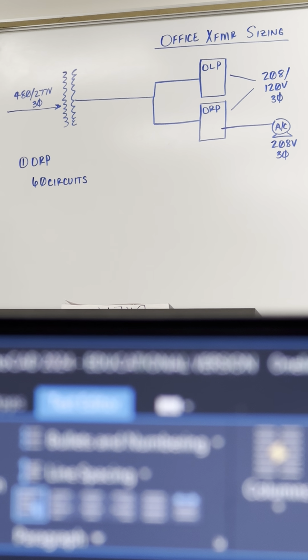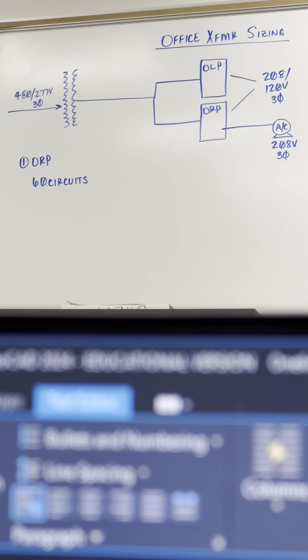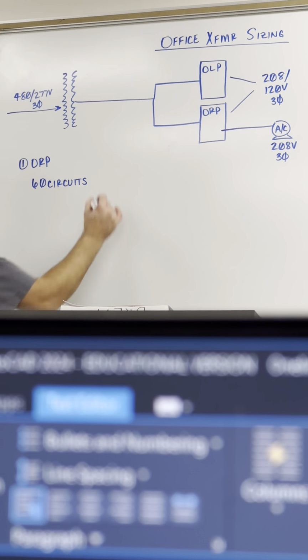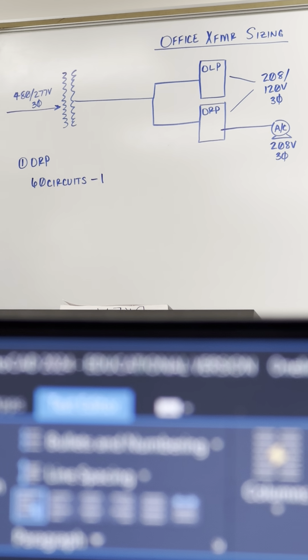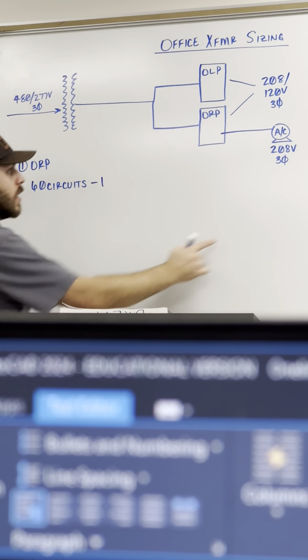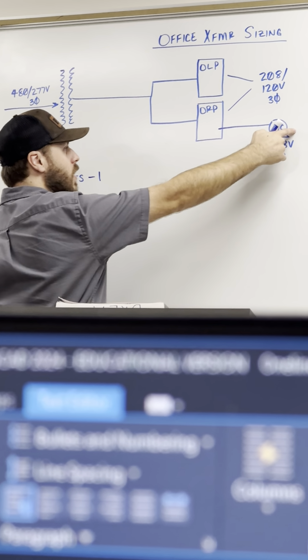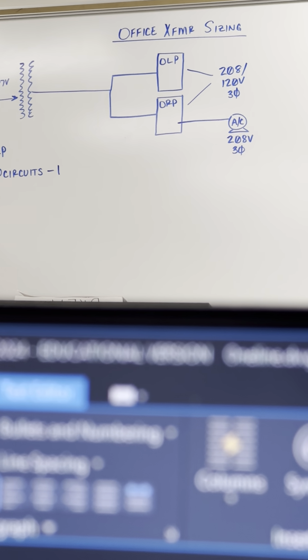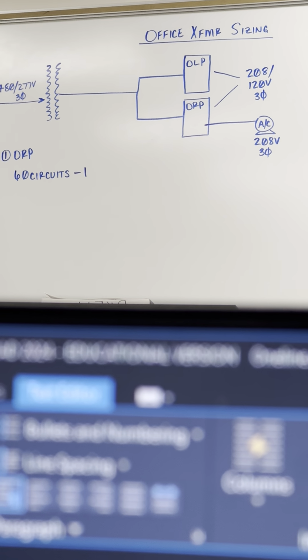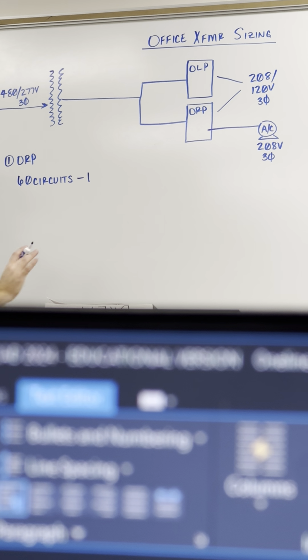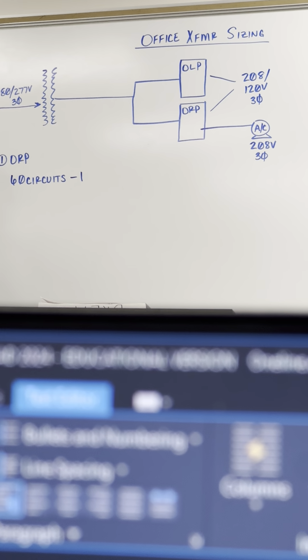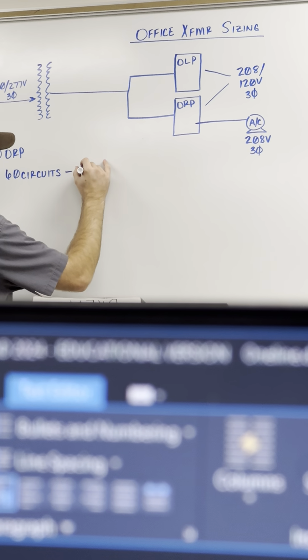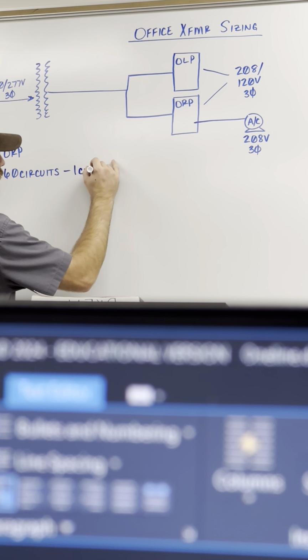If I got a total of 60 circuits, the first thing I'm going to do is subtract 1 from it. Why? Because this AC is part of that number whenever you look at your page there. Our AC is going to be a separate calculation in this process here, it's not a true receptacle circuit. So we're going to take 1 circuit and subtract it from it.